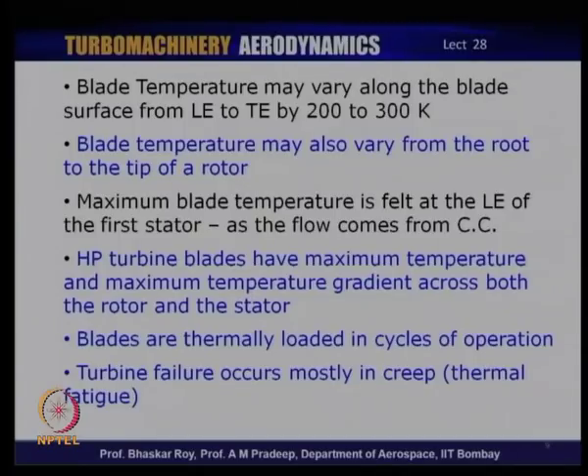This is a huge problem in terms of turbine blade life, and the cooling technology helps matters enormously. There are many blades where if you do not apply cooling, the blade would get charred in a matter of few minutes, whereas if you apply cooling the blade would last for thousands of hours of operation. If a gas turbine entry temperature is of the order of 1600–1700 K and the blade is not cooled, that blade will get charred in a matter of few seconds.